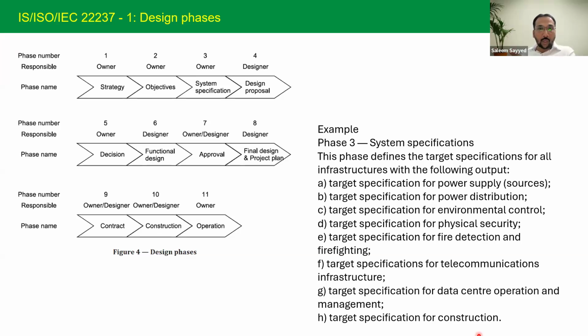Like your cooling, your building capacity, your megawatt, line size, phases of the building, the building configurations, your diesel storage, then the power substation capability. All those major components are decided in step number 5. Once that's done, your functional design of the system comes into the picture. The functional design is no more than the detailed design process, but the designer builds the complete design of the project, and that goes to the owner for approval.